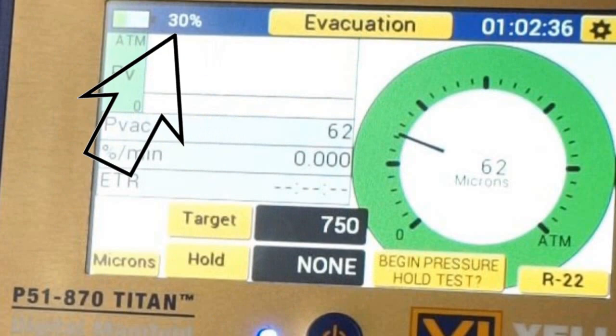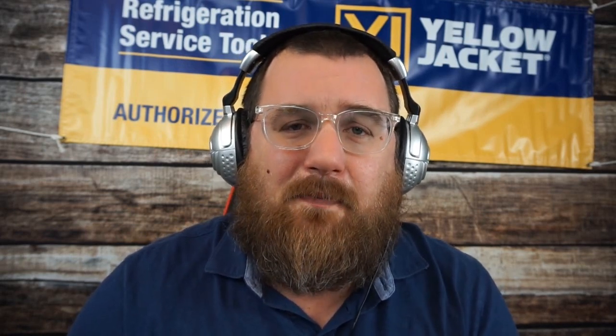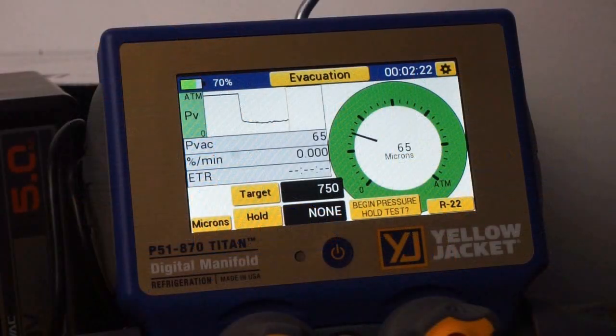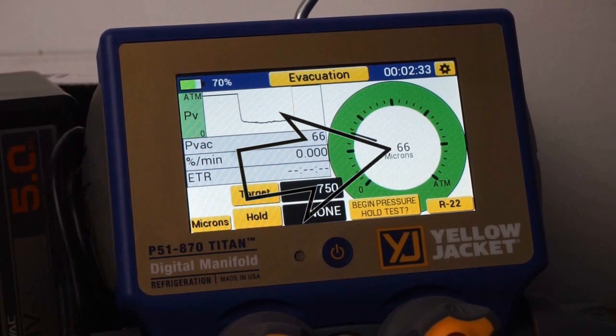So what we're going to do is put the test back into place. I'm going to charge the battery back up and charge the P51s back up — because we almost expended those as well, they were down at 30%. We're going to see if we can pull that ultimate vacuum down to 20 microns again with the same oil, which would prove it's not the oil; or if it doesn't pull it down, that indicates it might be the oil. It looks like the oil might be the culprit — we're going to do some further testing to prove or disprove that.